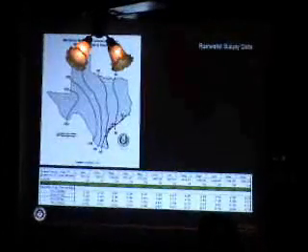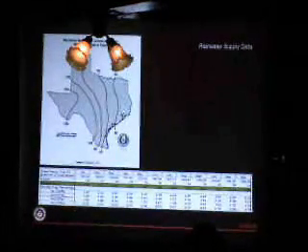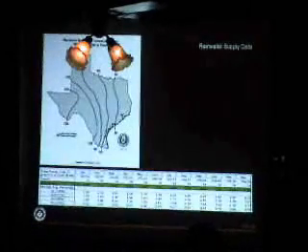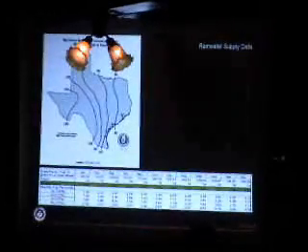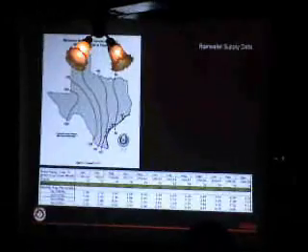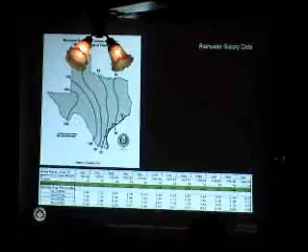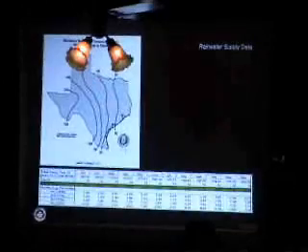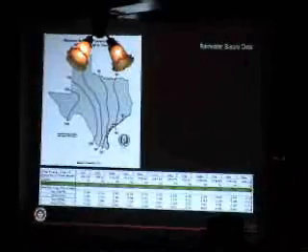Completely replacing the municipal water system. This allows us to not necessarily use the worst case scenario and the minimum, because we can rely on municipal water systems to make up for any differences in the water. So we actually took a baseline of 75% rainwater supply for the entire year. This allowed us some fluctuations if we had dry days. You see the second number, days without rainfall in Texas. The maximum days we would go without rainfall is 60 days. And during that time, municipal water systems and storage would take up the slack from missing rainfall.